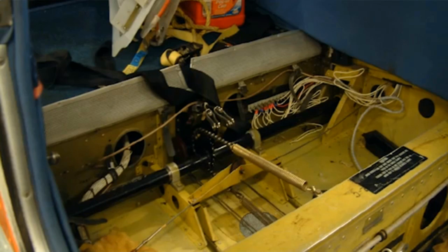Abnormal conditions may arise in an electrical circuit for a variety of reasons. For instance, a breakdown of the insulation on one of the cables carrying the supply to a component will cause a dramatic rise in the current flowing in that cable if it comes into contact with the metal of the airframe. There are several serious problems inherent in this situation.